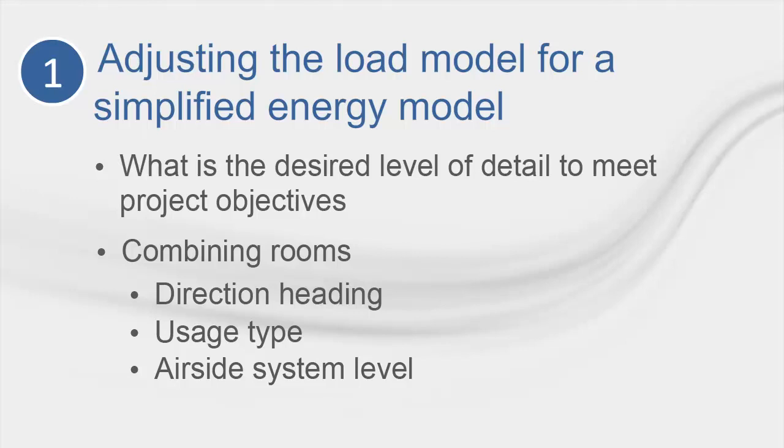When higher fidelity is necessary, zoning based on directional orientation may not be sufficient. In this case, the combination of spaces that are the same usage type, meaning no major parameter differences, such as thermostat setpoints, internal or external exposures, or continuous versus non-continuous ventilation rates, will help reduce the complexity of the model without a significant loss in accuracy. Now, some people may say that this is good for some energy modelers, but I'm doing a LEED model, and I need to be as precise as possible. Although I would agree the model needs to be precise, ASHRAE 90.1 encourages you to create thermal blocks in order to create a more simplified model.